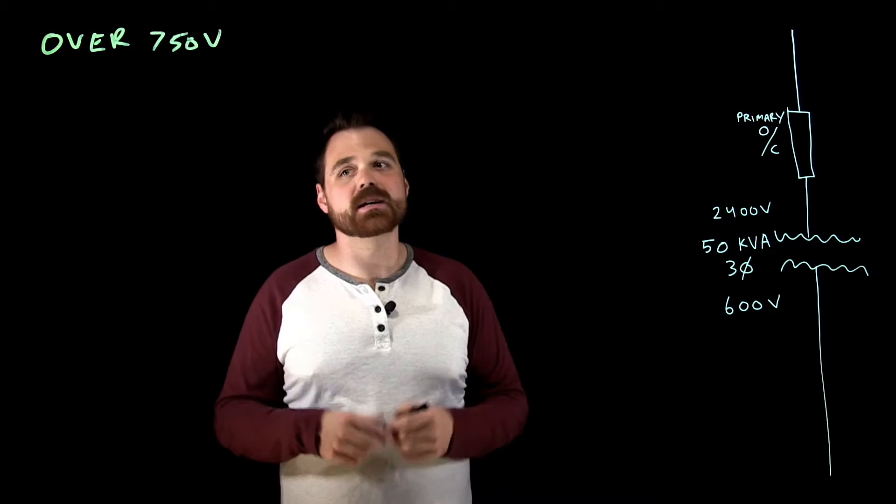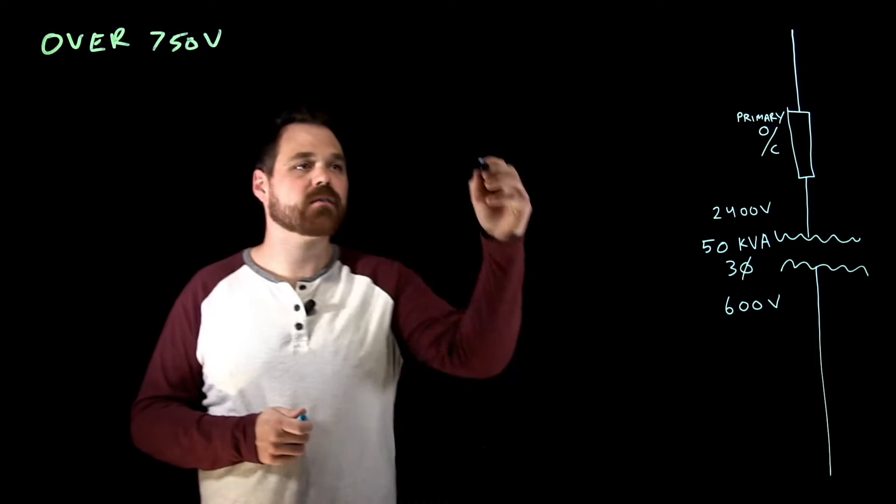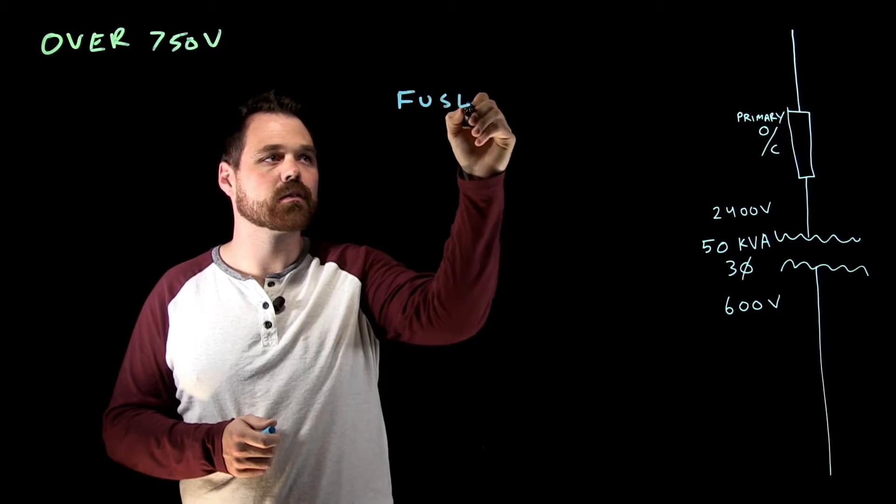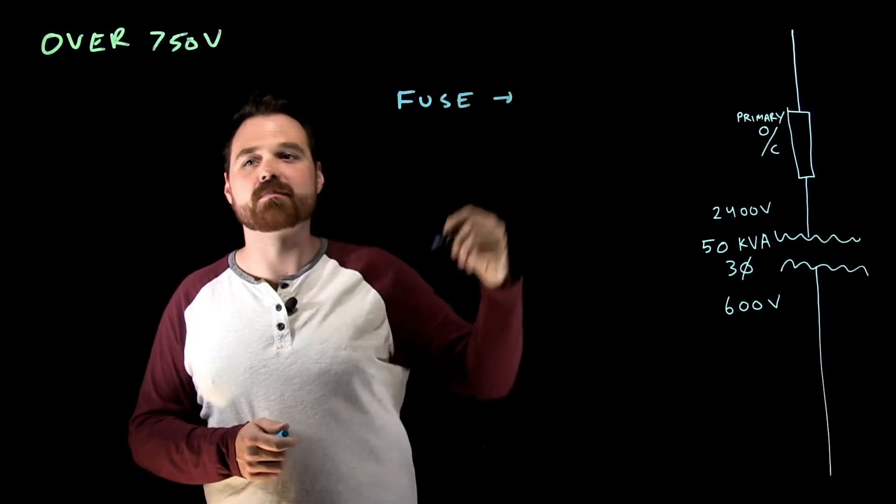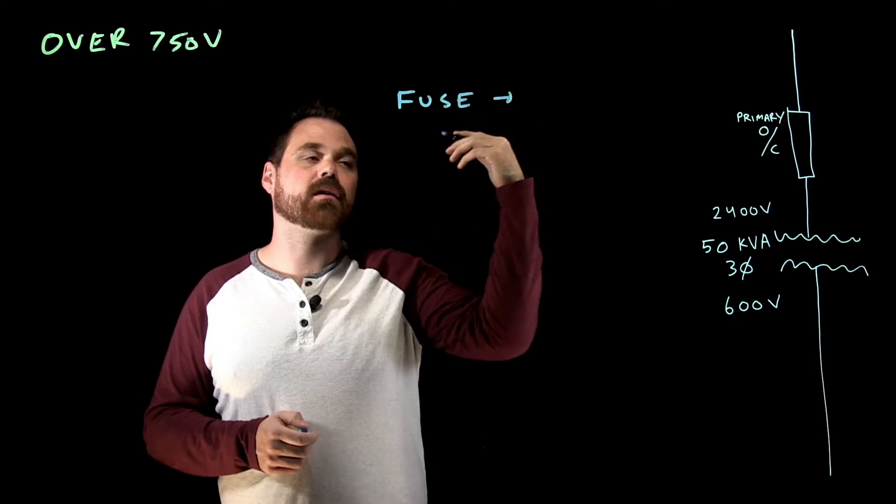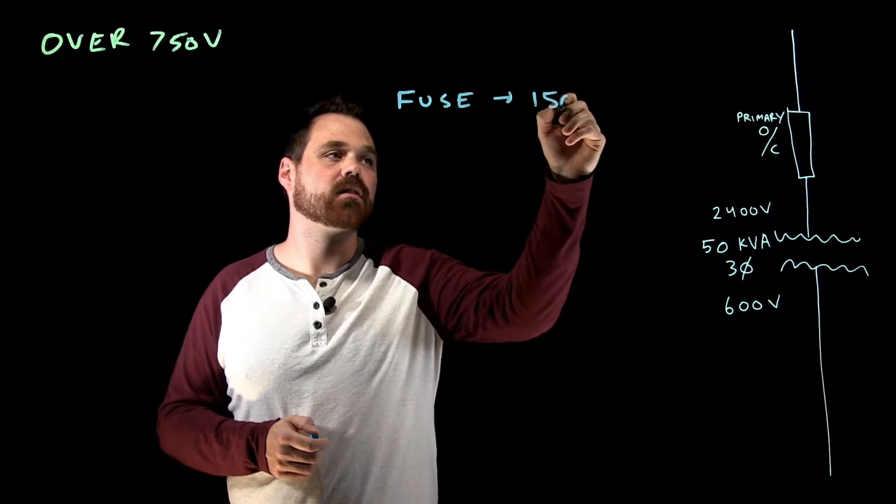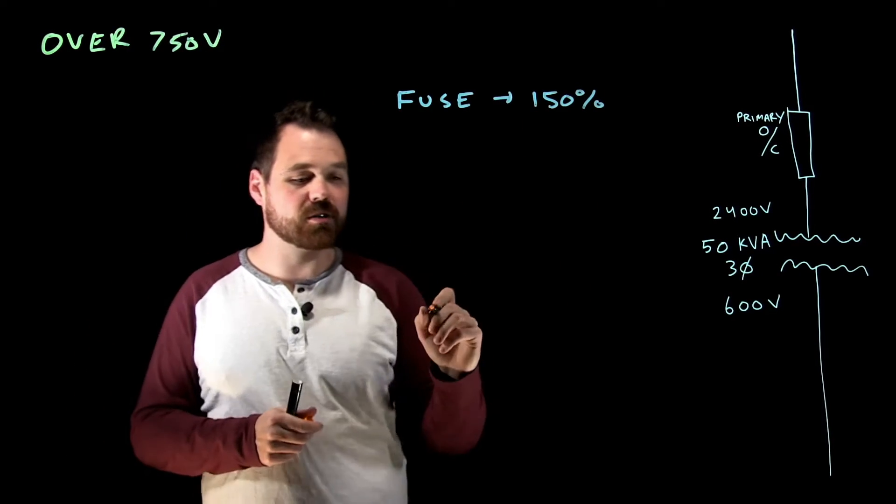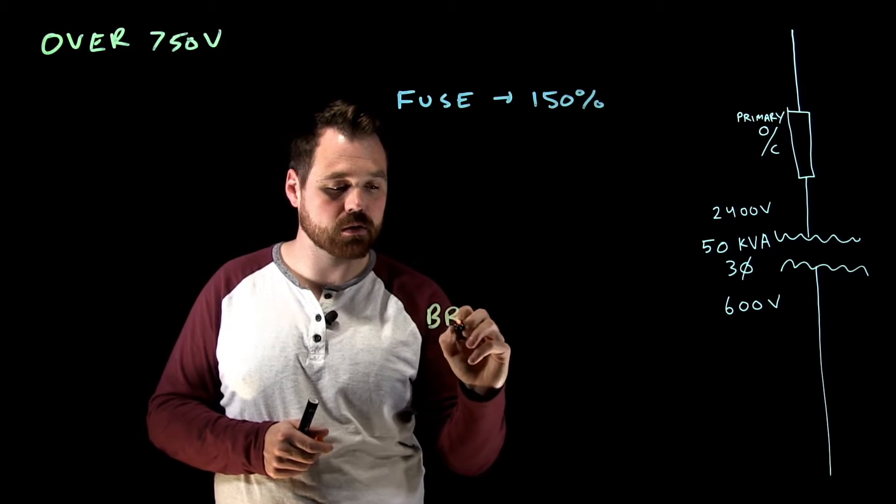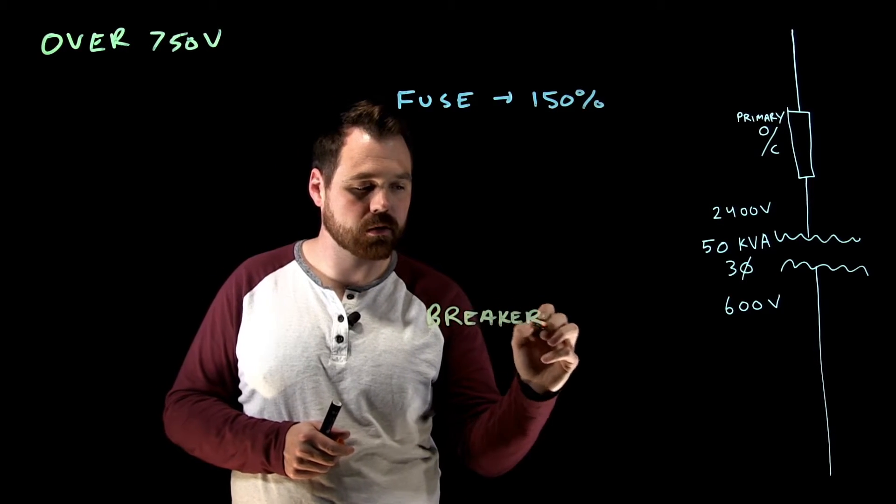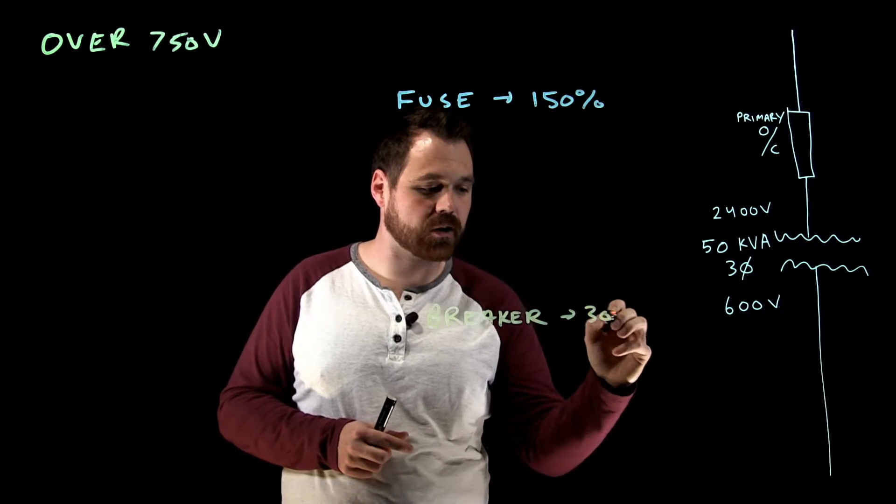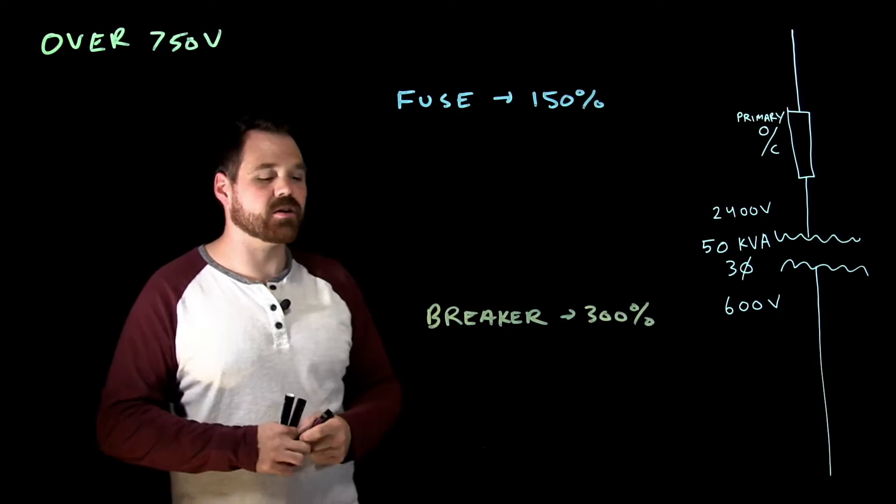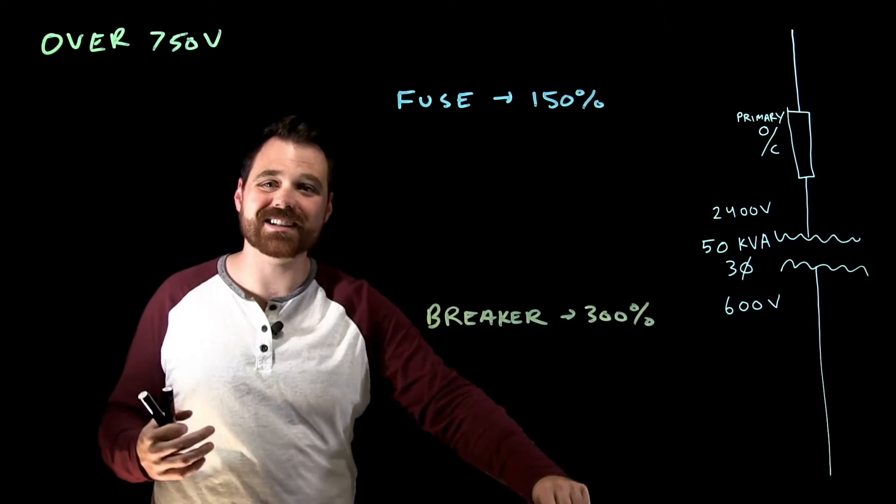Now what the code book tells us is if you're going to use a fuse, it's different rules, but if I'm going to use a fuse, my fuse can be based upon 150% of the current. If I'm going to use a breaker, it's based upon 300% of the rated current. So what I need to do here is I need to figure out what my rated current is.